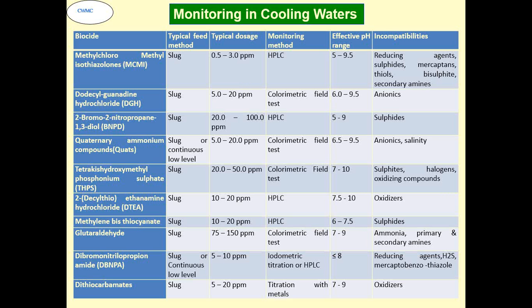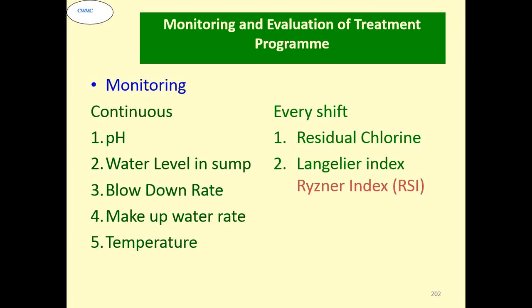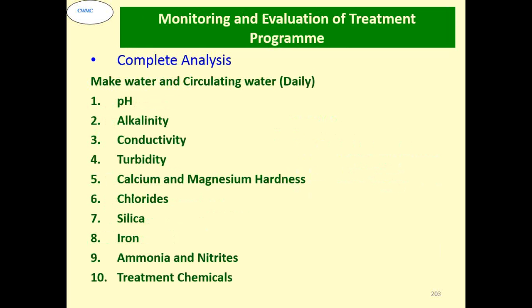Monitoring the cooling water, the various dosing levels for the non-oxidizing biocides. Monitoring has to be done generally every shift, at least once. pH, water level in the sump, blowdown rate, makeup water rate, temperature, residual chlorine, LSI or RSI, and then hardness, alkalinity, etc. need to be carried out every shift. This is the complete analysis.